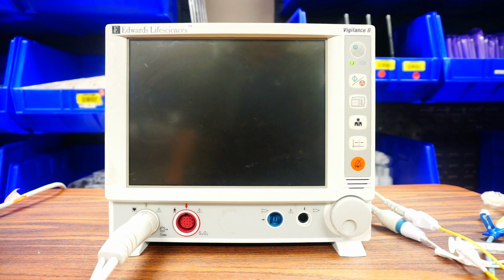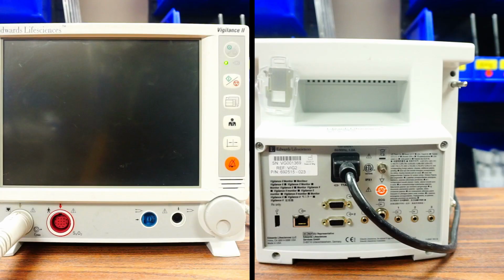So now I'm going to show you how to set up your Swan when you are not able to use the Hemisphere. Rather, you need to use the Vigilance 2. Reasons why you would use the Vig 2 instead of the Hemisphere are if the Hemisphere is currently being used, or if it's broken. If not, then you're going to go for your Vig 2. We have 2 of these on the unit still.